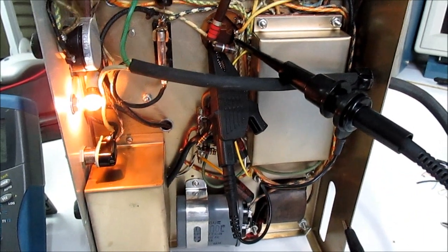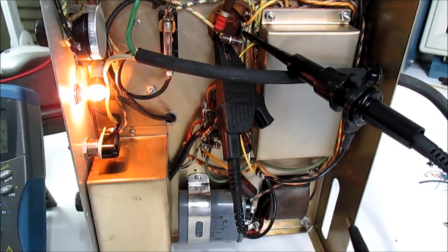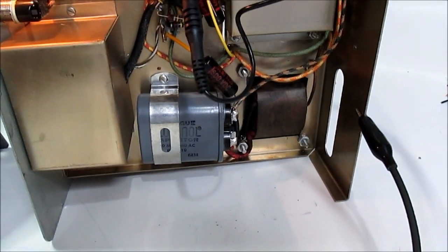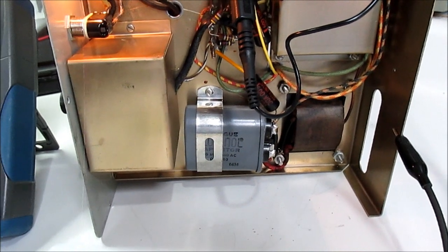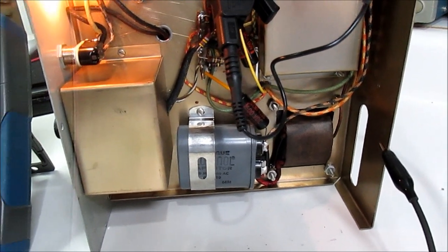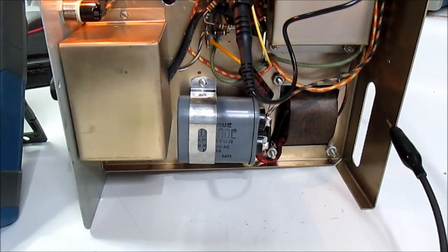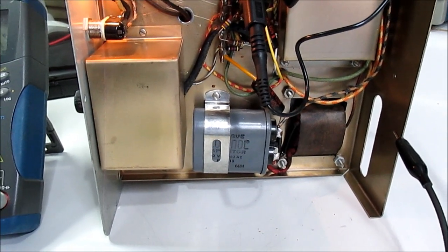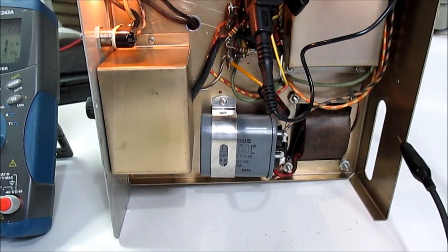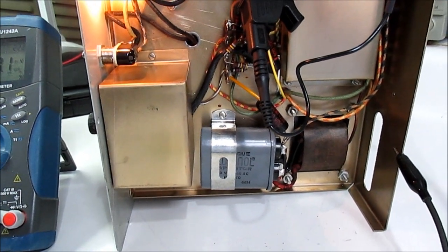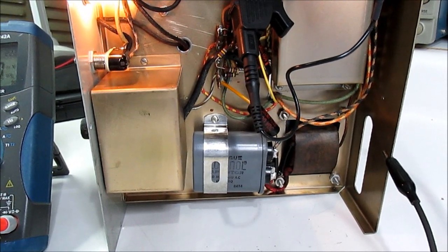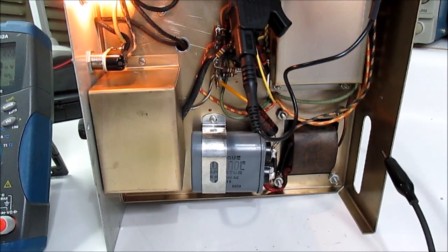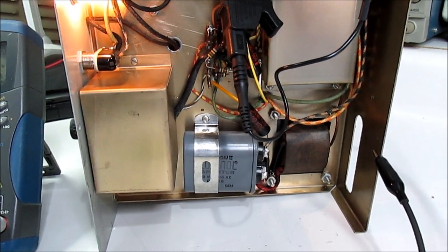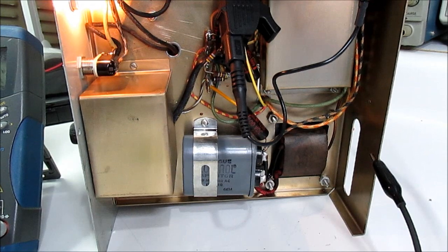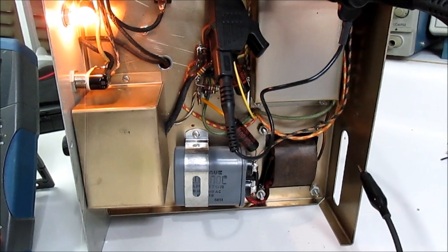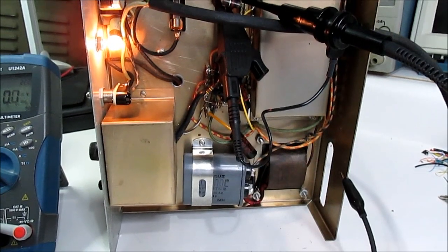And if you look at the schematic again, as we were doing earlier, it kind of folds back into this oil-filled motor start type cap that's across that transformer that seems to be hotter than normal. My personal experience with these kind of caps: I had an old air conditioner that was drawing huge currents and melting the power cord and popped a breaker at one point. The root cause was an oil-filled cap like that on the fan or the compressor motor that went open circuit. So I'm kind of wondering about that thing, and we'll see if we can figure out some way to check that out in case that is the problem with this thing.